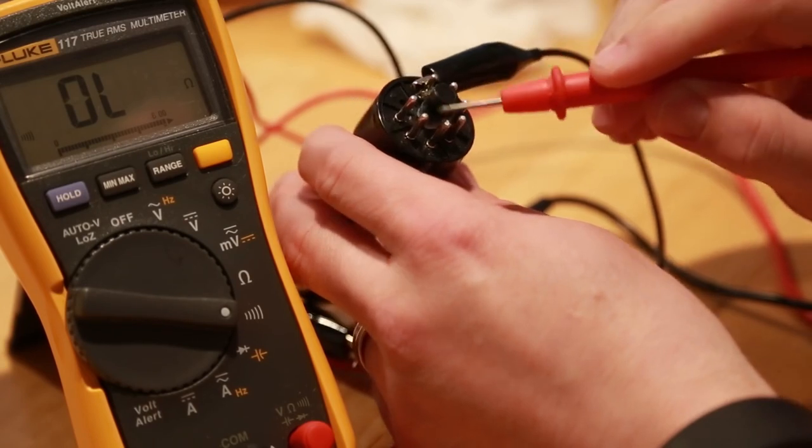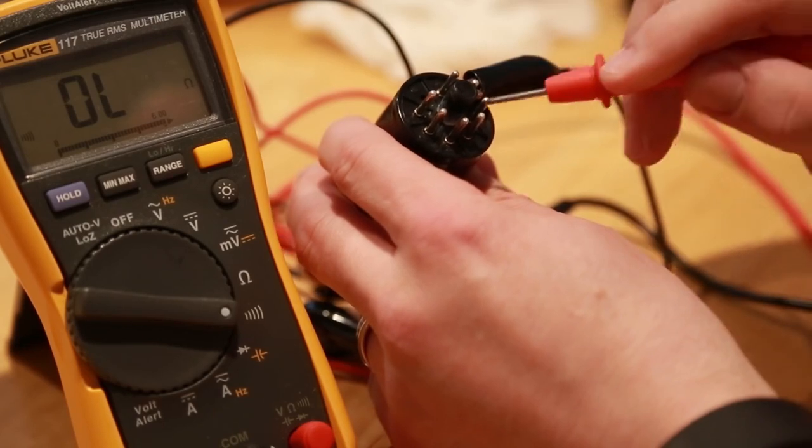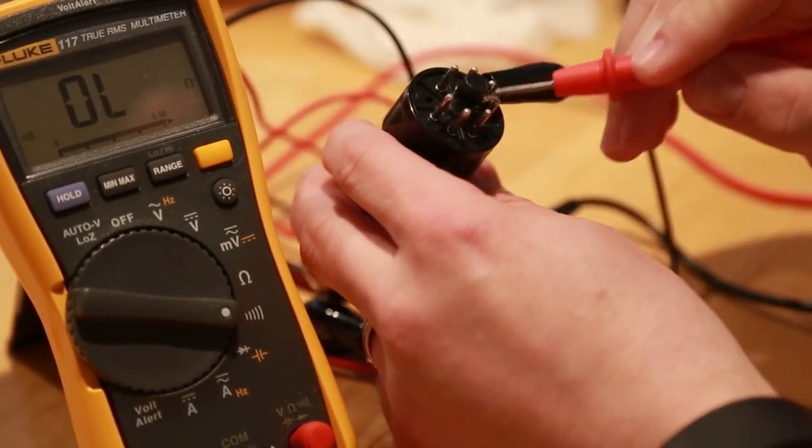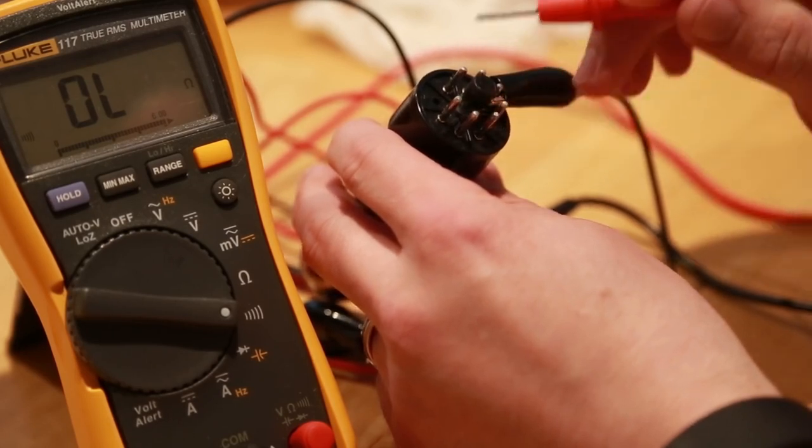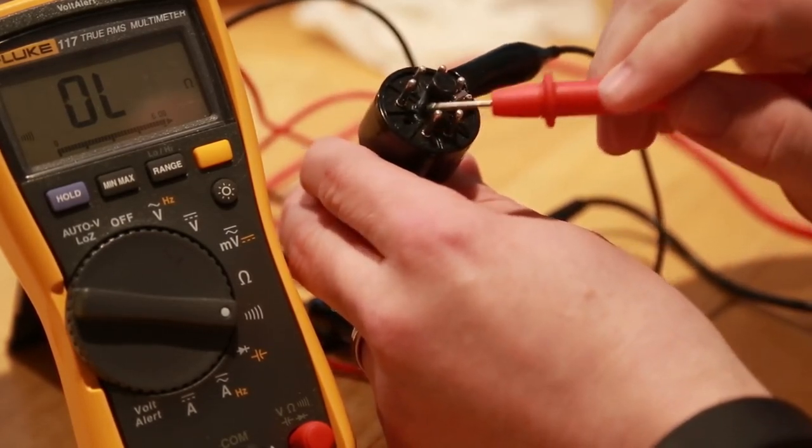You should also test all of the other pins because I should not have continuity on those. Then you can go through a daisy chaining process of testing all of the pins to make sure no other continuity happens except on those that are supposed to, like the heater pins.